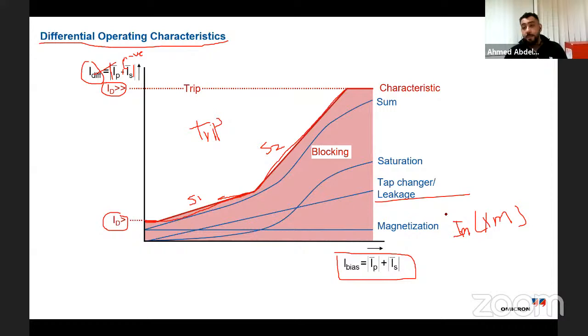And also the tap changer. In many cases, in a big grid like Saudi Arabia's SEC, especially during the summer, they need to regulate the voltage of the network to maintain the voltage at your socket around 220 volts. So they sometimes need to increase the voltage at the substation or decrease it to avoid overvoltage and undervoltage. This happens with something we call a tap changer. We have two types of tap changer: the off-load tap changer and the on-load tap changer, OLTC. OLTC is most common, because with the off-load one, I need to switch off the transformer, change the tap, then switch on.